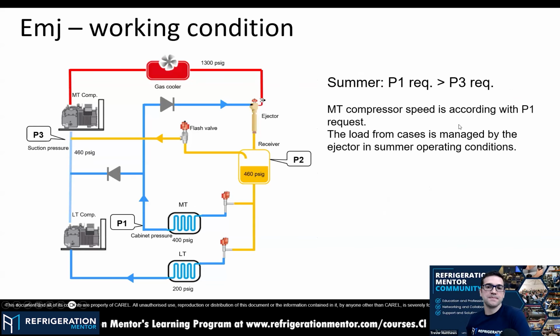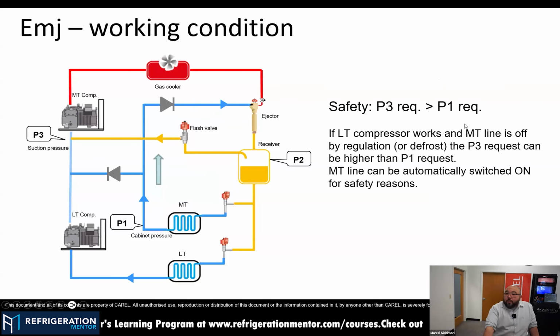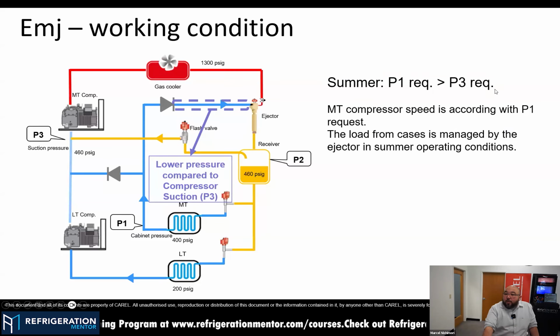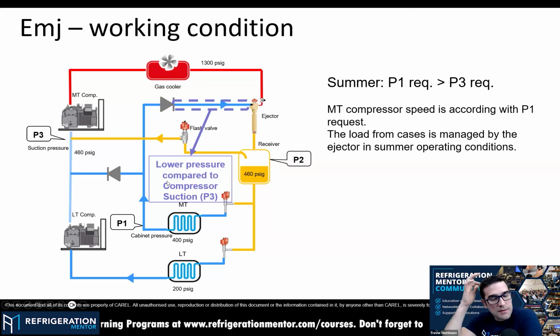Yeah, makes sense. So in summer, as we mentioned, we have this higher pressure coming from the gas cooler, transferring this energy into compression from the suction MT, and my mass flow will go partially or 100% through the ejector port of the system here. This is where we have a lower pressure compared to the system here. Okay, yeah, so makes sense.